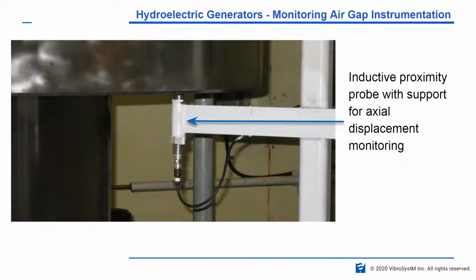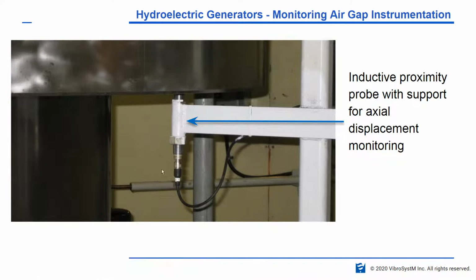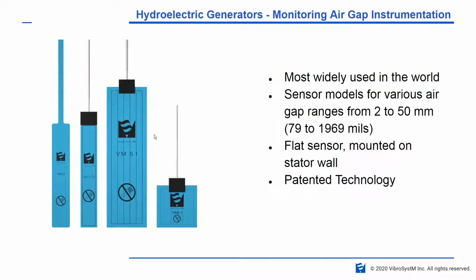In fact, this case here is one of the cases I used during my training courses to show why axial displacement monitoring is important. This unit had a thrust guide bearing wipeout, and they made a whole list of repairs, not only to the thrust guide bearing, but they also made some modifications to the turbine and so forth. And when they put the unit back online, within a month the unit failed again, and this little sensor provided the information they required to be able to determine what the issue was. So we'll see that also in some videos.